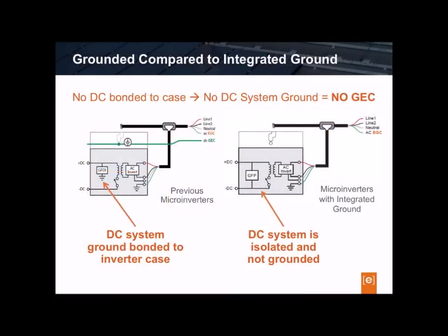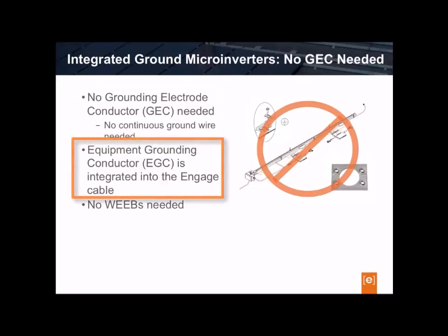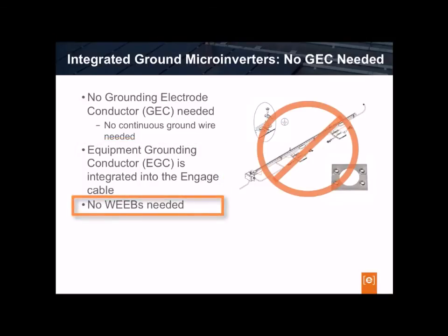Looking at the two microinverter diagrams side-by-side, the difference is clear. Isolating the DC circuit makes all the difference and satisfies NEC requirements for ungrounded PV power systems. Because the DC circuit is isolated and insulated from ground, the Enphase microinverters with integrated ground do not require a grounding electrode conductor, or GEC, connected to each microinverter. And since the microinverter EGC is incorporated into the cabling system, no additional grounding materials such as the continuous copper grounding wire or WEEB grounding washers are needed.